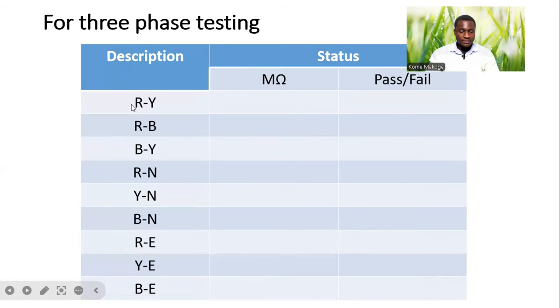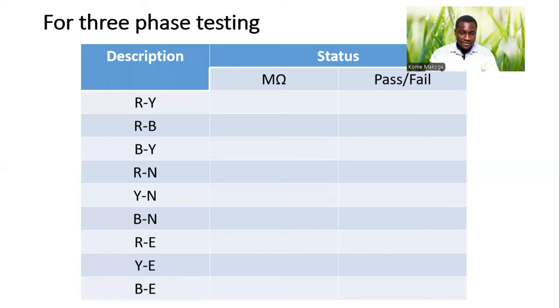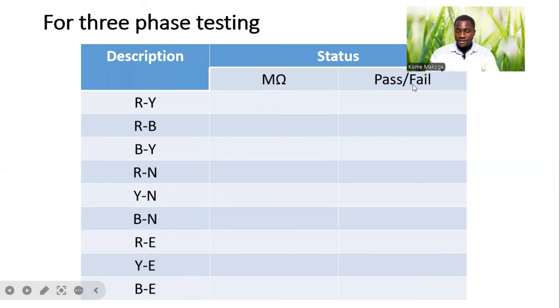For three phase, we will test between red phase and yellow phase, red phase and blue phase, blue phase and yellow phase, red phase and neutral, yellow phase and neutral, blue phase and neutral, red phase and earth, yellow phase and earth, and blue phase and earth. We register the value obtained in megaohms after carrying out the test, and then put the status — either pass or fail.